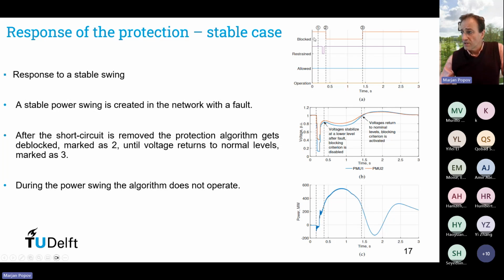So what we see in this network here is, we have first a normal operation. So during normal operation, the out-of-step protection is blocked, but also at the same time, it is restrained. Instant one denotes that the fault current occurs. Protection is still blocked because it's not an out-of-step condition. It's a fault current. At the same time, the protection is also restrained, right? Instant two denotes that the fault is removed. Well, actually, the fault is previously removed. However, at instant two, the conditions are fulfilled so that the protection is deblocked. However, it is still kept restrained. Until it is kept restrained, it will not operate.